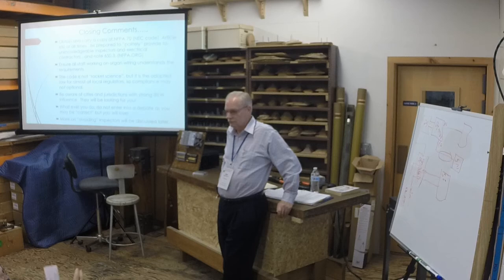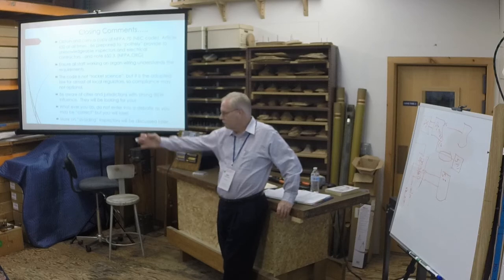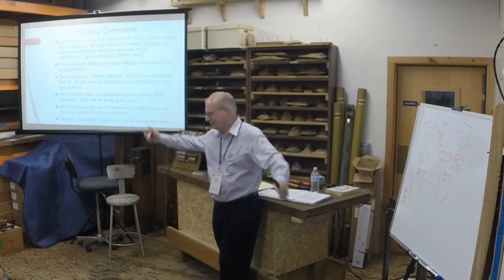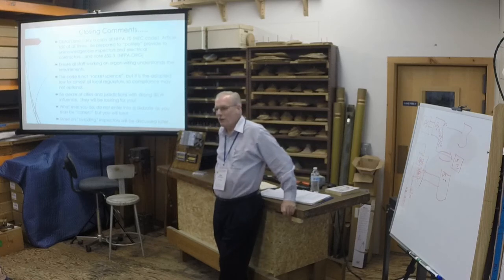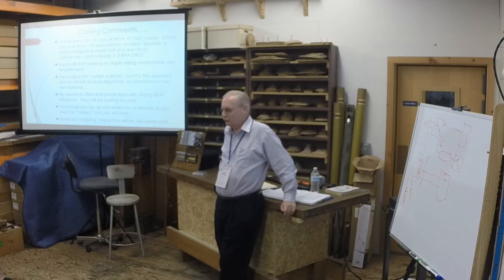The issue is cloth covered cable is going to unravel, the insulation will deteriorate over time, and if it gets wet, that's the big thing. If it gets wet, it's part of the resistance equation. And if it gets wet in the wrong place, it's never going to dry. It may begin to rot, which lowers its resistance and increases the heating capacity. That's not good business.